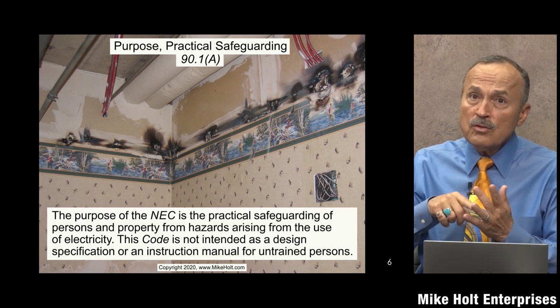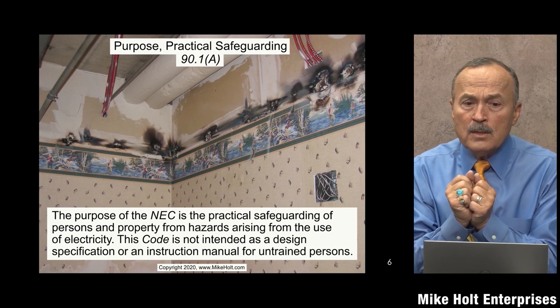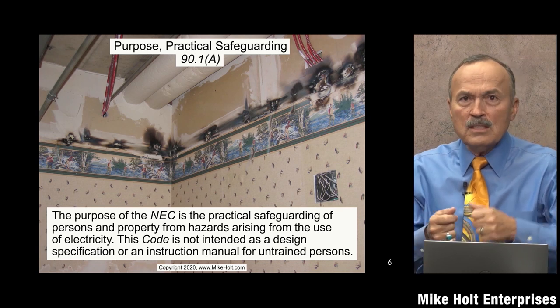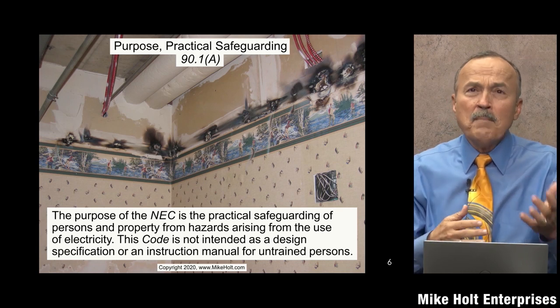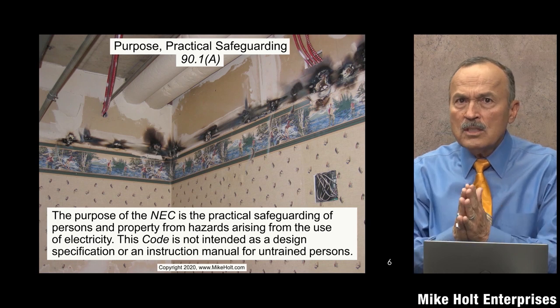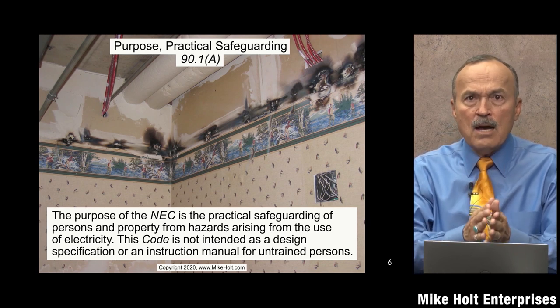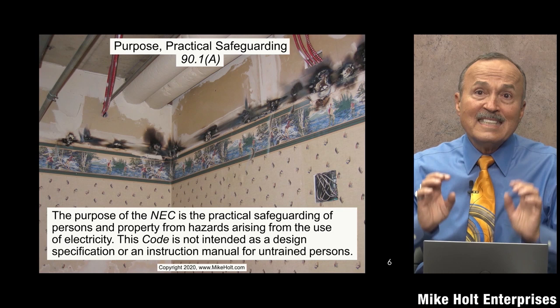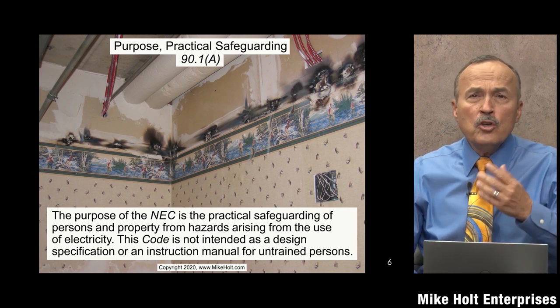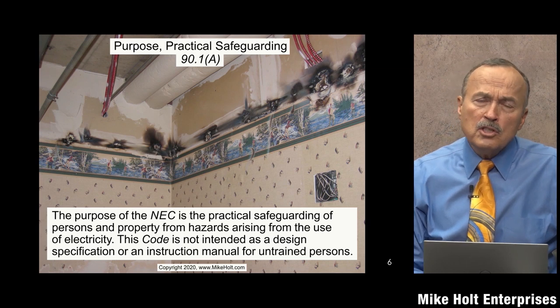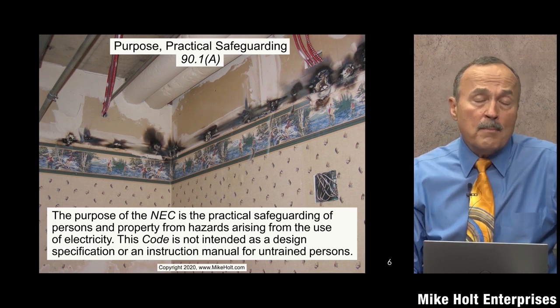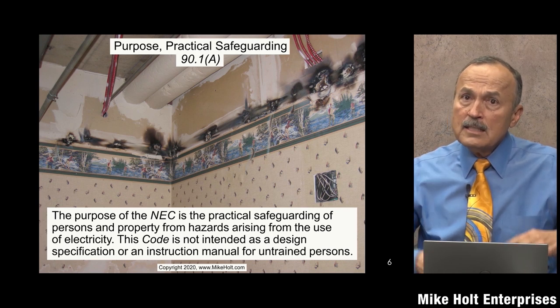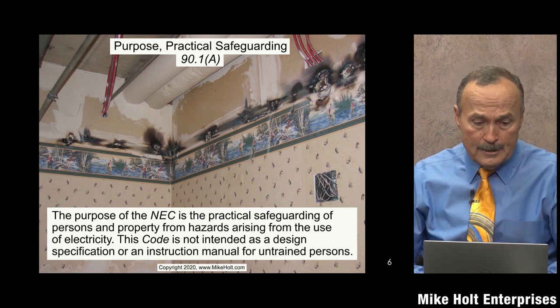We want to install per the National Electrical Code and in accordance with the manufacturer's instructions. Even if done perfectly at completion, over time someone might disturb something, something gets loose, and it's not maintained. An electrical system from the moment you finish it is beginning to fail. We want to install things so that when they fail, they fail safely — that's what 'practical' means.